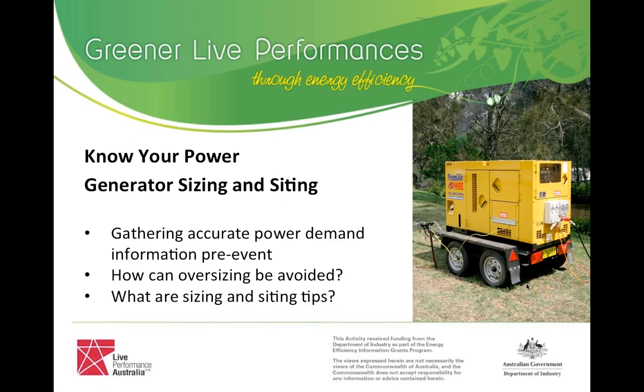That knowledge is incredibly valuable. When you're talking about reducing the number of generators, are you talking about reducing total KVA at the same time, or reducing your distribution by putting more onto larger generators? We've managed to maintain the same number of generators while our site has grown by looping different areas, getting a larger generator in one area and linking it to more areas.